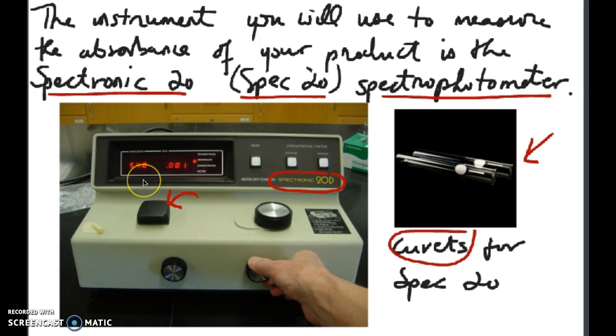Okay, then the next thing is you need to adjust the absorbance so it's 0, because remember, this is the same as taring the balance, so you want to make sure that number goes to 0. Before you can get to adjusting that number to 0, first you have to change the mode of the spectrophotometer so it measures absorbance. So you press this mode button so it toggles from the top to the second one. Now you're in absorbance.